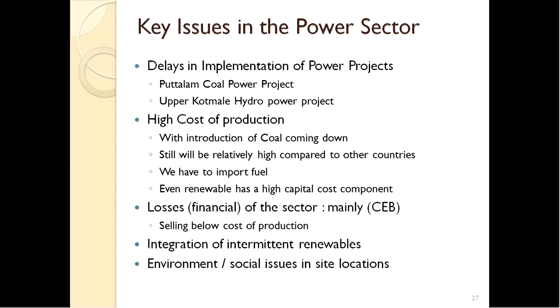It may be because in the Puttalam region, where most of our wind plants are, there's an increase or decrease in wind. With other power plants, when there's a requirement, CEB can ask a plant to respond. For example, control operators can ask the Kotmale power plant for 70 megawatts, and the hydro machine can start up, synchronize, and reach full load in maybe 10 to 15 minutes, even 5 minutes. Even if Norochcholai or Lakvijaya is running at a low output of about 200 megawatts, the operator can ask them to increase to 275 megawatts, which takes about an hour or two, and they will do it. But we can't ask a wind power plant to do that.